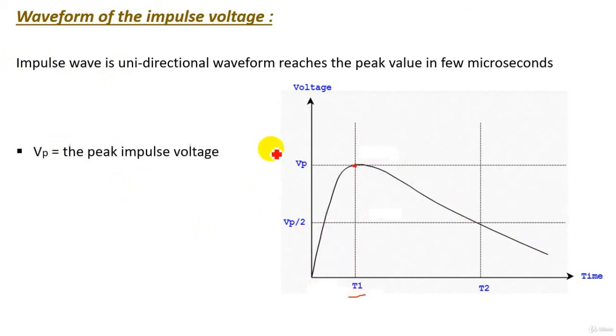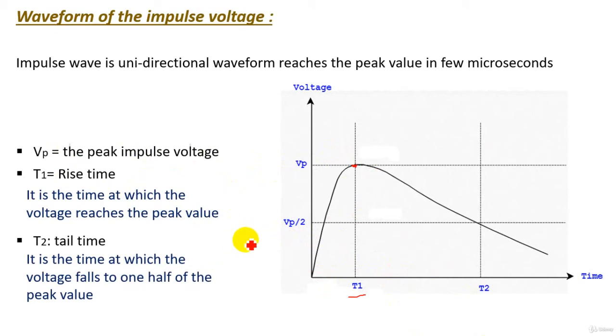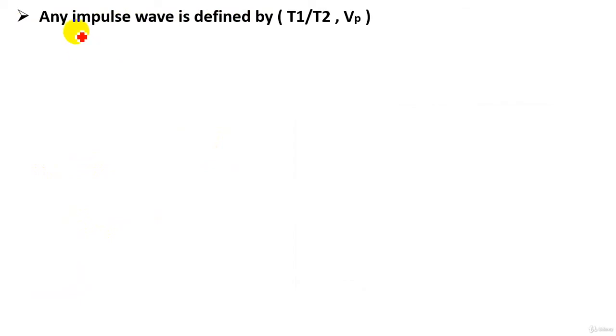The key parameters are: Vp, which is the peak impulse voltage; t1, the rise time — the time at which the voltage reaches the peak; and t2, the tail time — the time at which the voltage falls to one half of the peak value. Any impulse waveform is defined by t1/t2 and Vp.